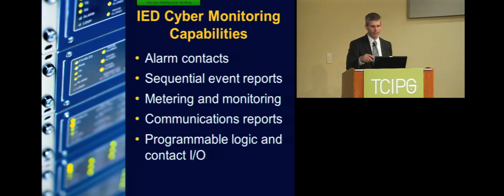One of the things that we did way back with the first relay is we also used the alarm contact to pulse. And so if you were to go into the access level where you could change settings, the contact output would pulse. And it's essentially an independent channel from the regular relay to signal somebody that they got into the relay, which an operator in a SCADA system could say, hey, there's somebody in the substation, there shouldn't be anybody in the substation, why did the contact alarm pulse? So these are little subtle things you can use today that are built into the devices.